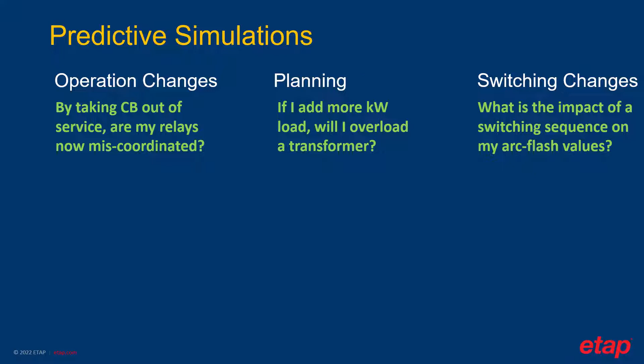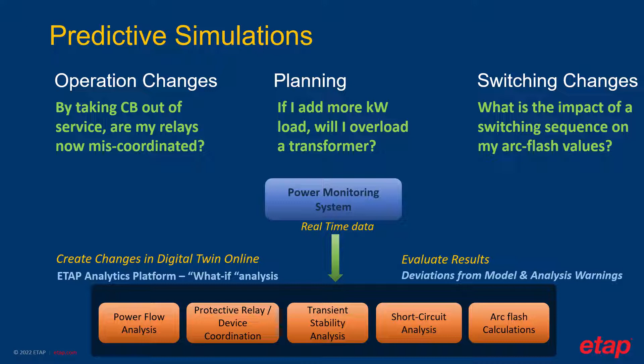With the predictive simulation running with online data, ETAP takes a live snapshot of online conditions such as circuit breaker status, operating load and generation, bus voltages, and other measurements to the analytical engine. Then users can take the online snapshot to create changes within the digital twin, and this is where users can create their scenarios for changes with online conditions and run the simulation. Finally, users can evaluate the result of the simulation and take action. This could be an answer to something like, is it safe to take this action, or will it cause instability on my system? Note that the simulations are not limited to real-time data. You can also use historical data to perform any type of predictive simulation.